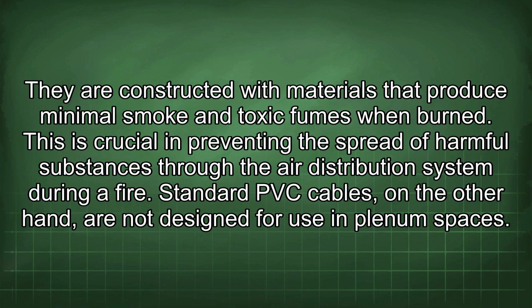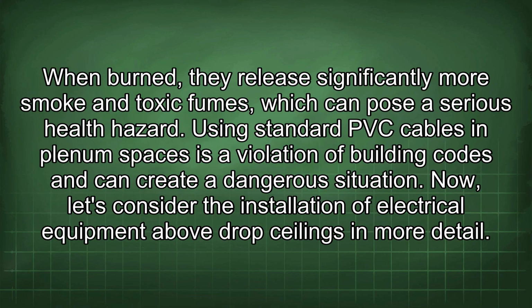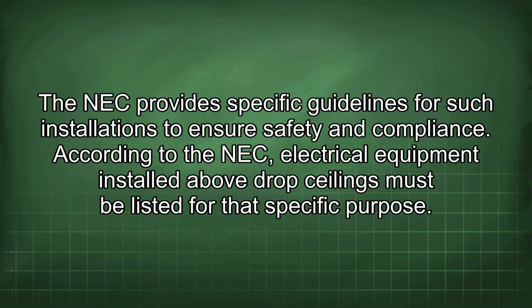Standard PVC cables, on the other hand, are not designed for use in plenum spaces. When burned, they release significantly more smoke and toxic fumes, which can pose a serious health hazard. Using standard PVC cables in plenum spaces is a violation of building codes and can create a dangerous situation. Now let's consider the installation of electrical equipment above drop ceilings in more detail. The NEC provides specific guidelines for such installations to ensure safety and compliance.